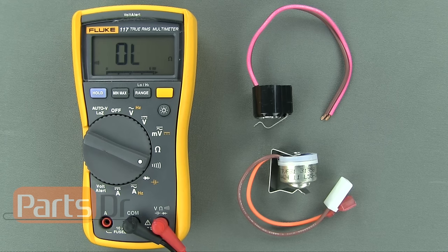If the thermostat does not pass these continuity tests, then you should replace the defrost thermostat.